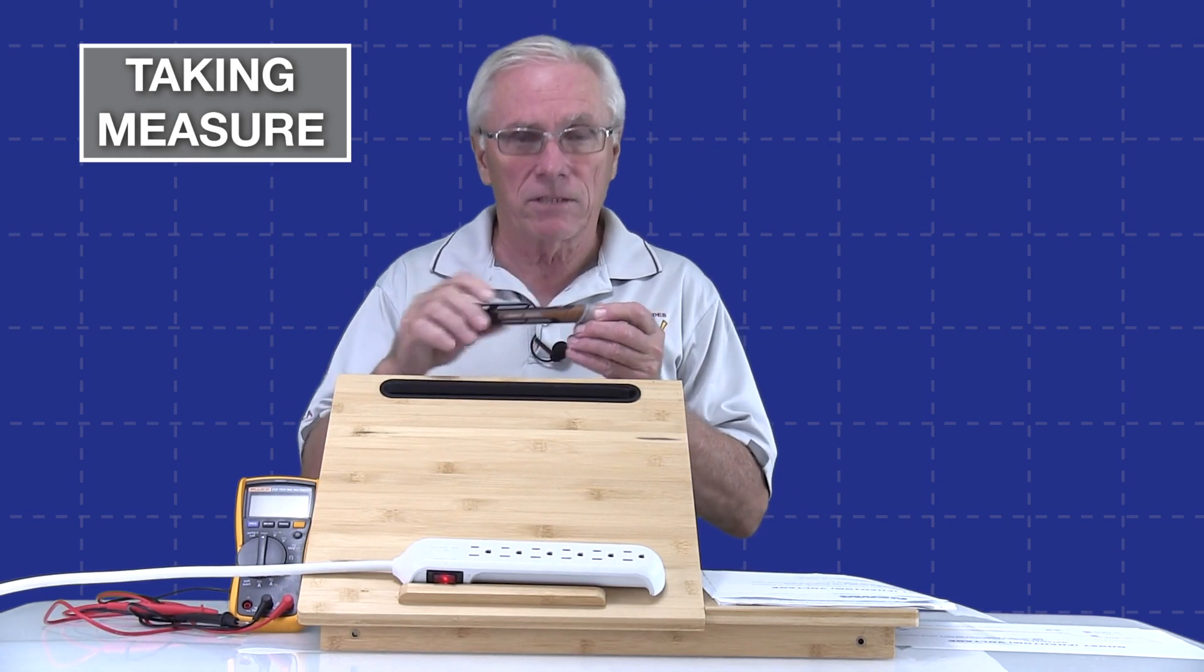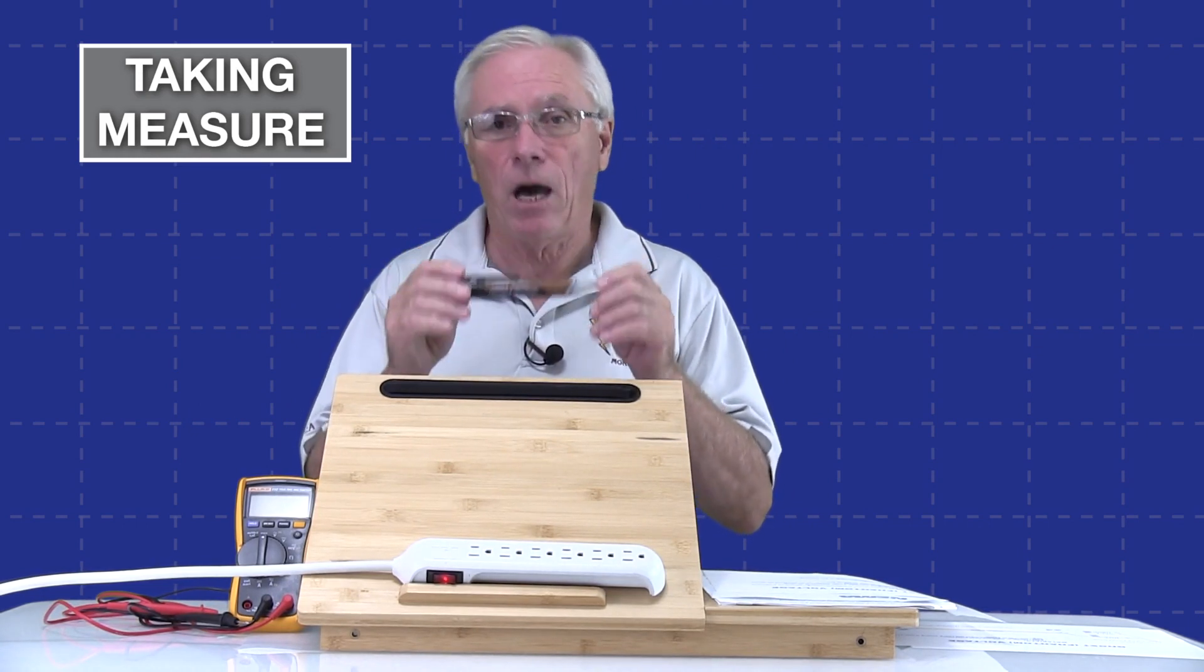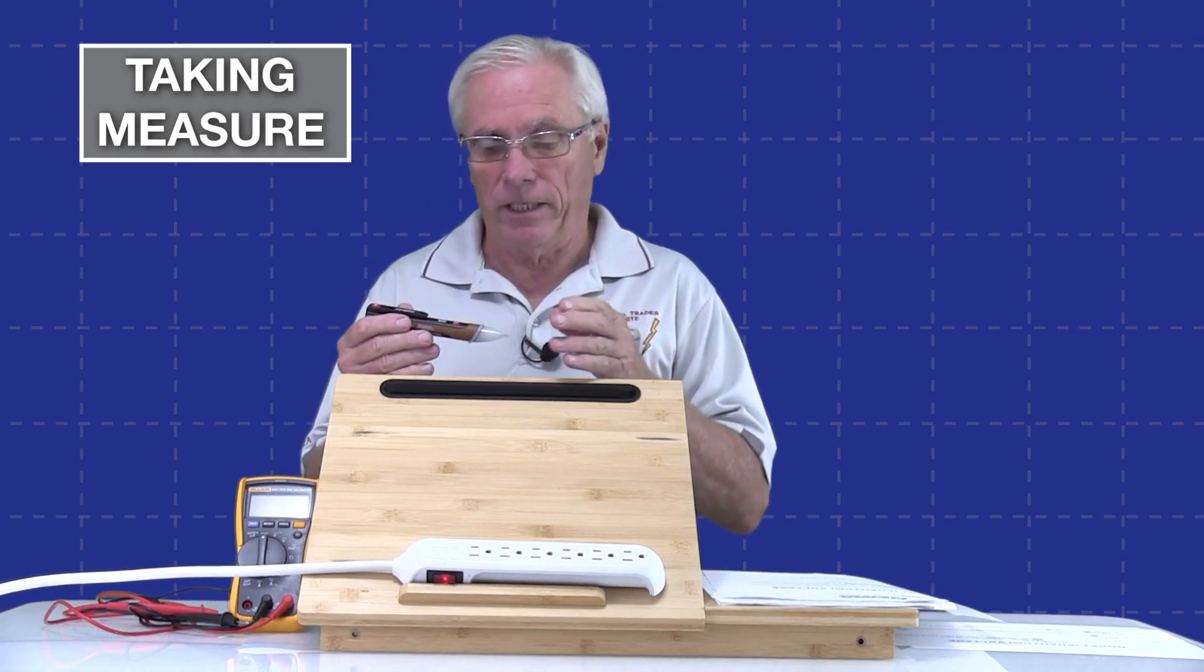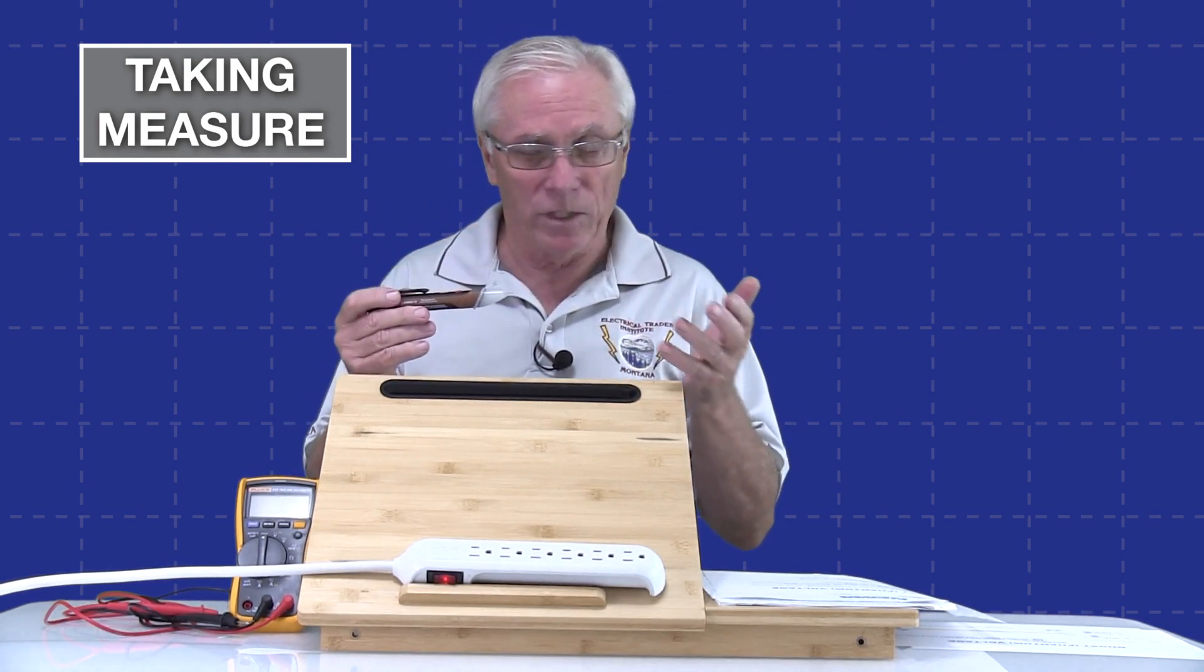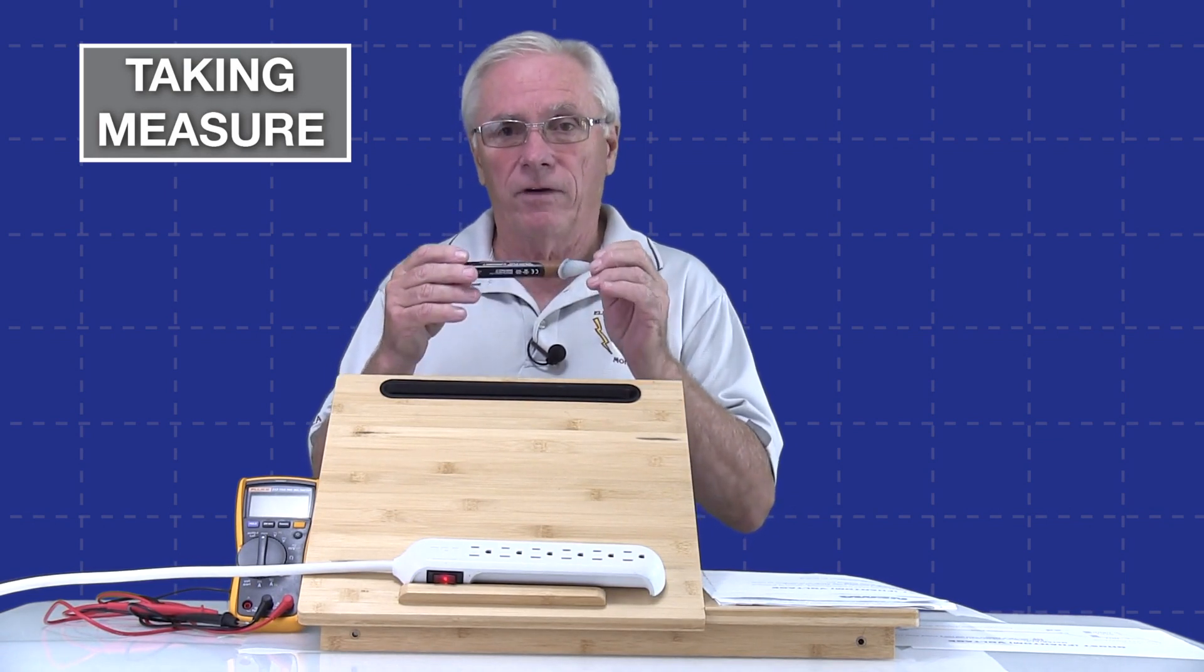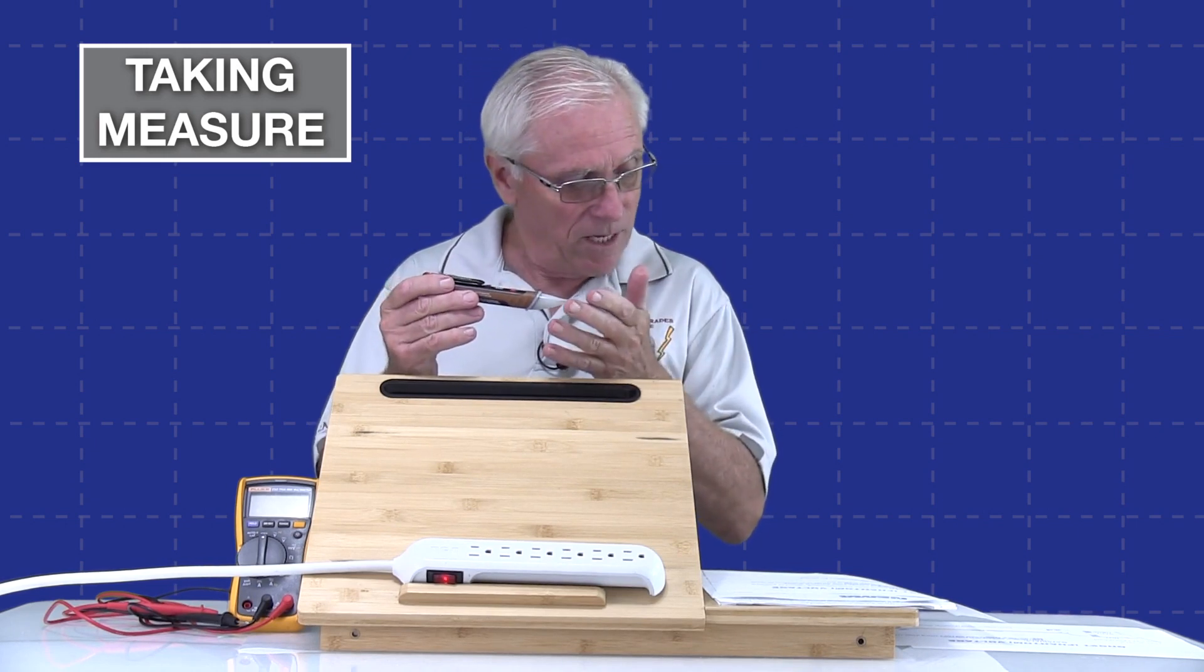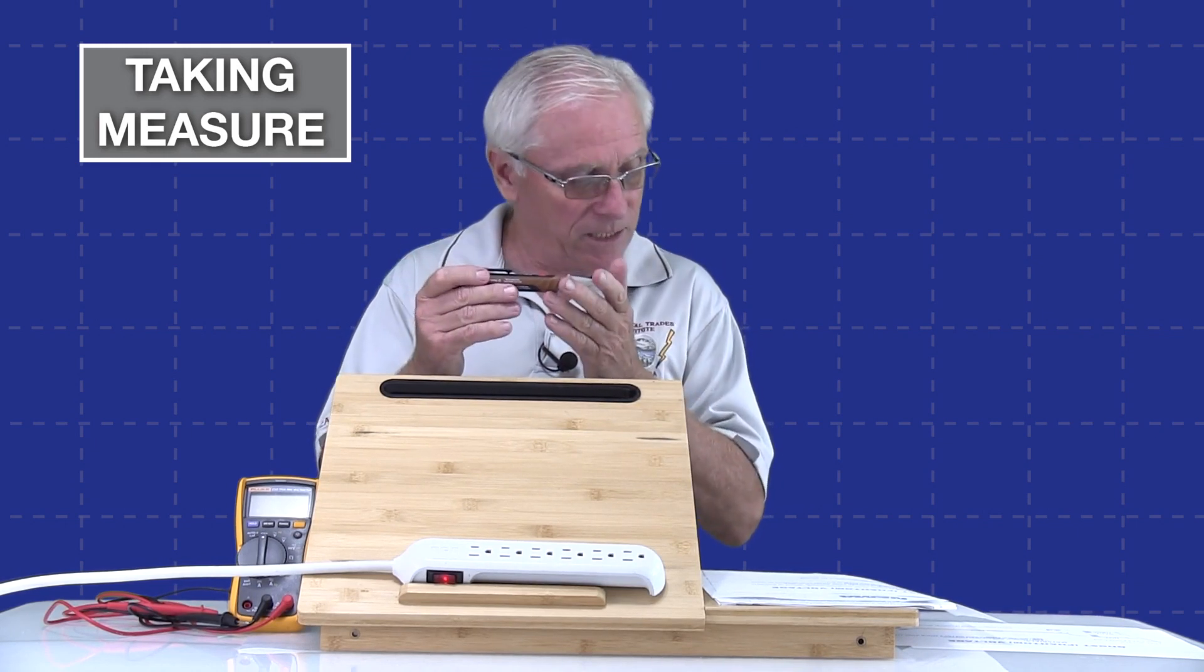These testers, as we explored in a previous video, work by capacitively coupling with an energized AC circuit. It has to do with the AC voltage in the circuit. I want to stress these do not work off of inductance. They work off of that electrostatic field and they have to be an AC circuit.